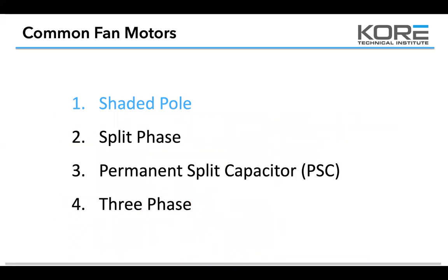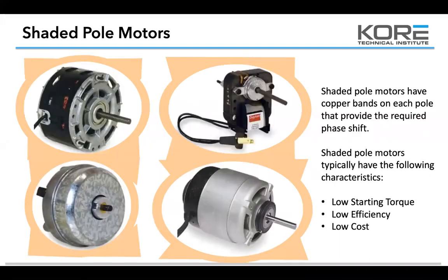So we're going to talk about shaded pole. We still see a lot of shaded pole motors. It's going to be your 5411s, your cannonball motors. It's going to be a lot of your condenser fan motors, the ones without the capacitor. So it's going to be your skeleton motor or C-frame motor. If you guys can see my cursor, you've got your pretty typical, larger condenser fan motor. You've got your 5411 cannonball motor. You've got your C-frame here, and then this is just another type of condenser or evaporator motor, like your 35 to 50 watt condenser fan motor that we see in some of the bigger condensing units.